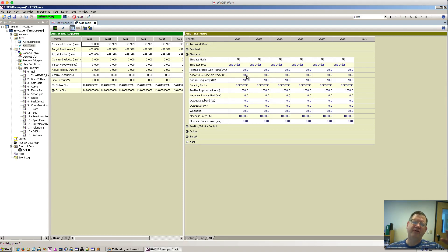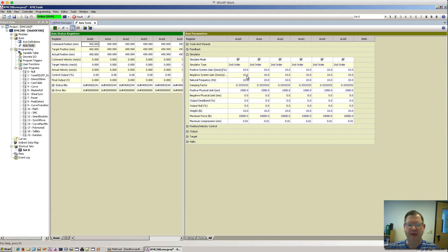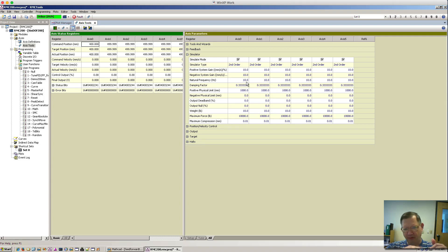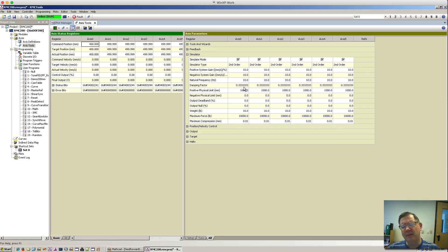Normally on a hydraulic system there's a rod so the gain is different in both directions, but I'm not going to play with that today because it's not really pertinent to feed forwards. I have a natural frequency of 10 hertz, which is dependent upon the spring constant — the square root of the spring constant over the mass — and there's a formula for calculating all that for hydraulic systems. The damping factor is a hard parameter to estimate, but a very typical one for hydraulic systems is about 0.333, so that's what I'm using.